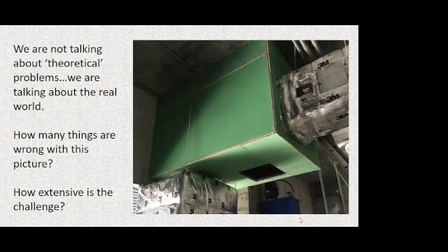We also see, and I can see from the floor, that there is no proper fire stop at the penetrations of the drywall box. The fire stop matters as much as the duct. If the duct is going through something fire rated, it doesn't matter if the duct stays there for the 2 hours if the fire goes right past it and through the joint to the other side of the compartment. We fundamentally failed. Every fire rated duct is tested with companion fire stops. There's no mystery here. The fire stops matter as much as the duct. Match them up, follow the entire assembly.